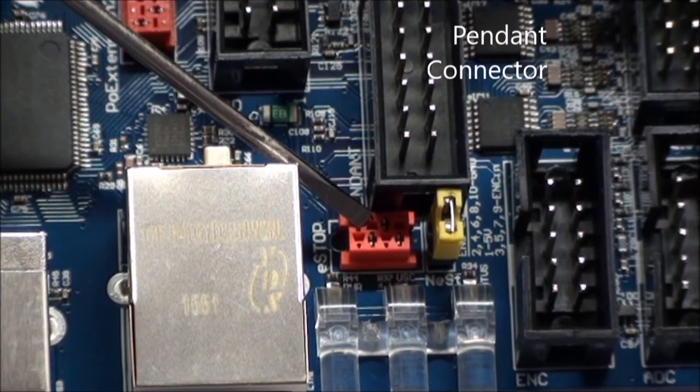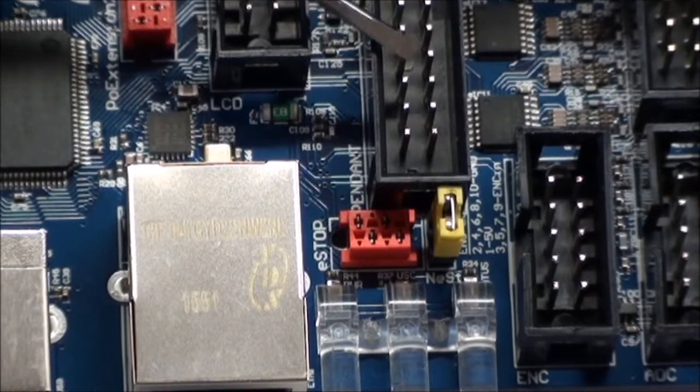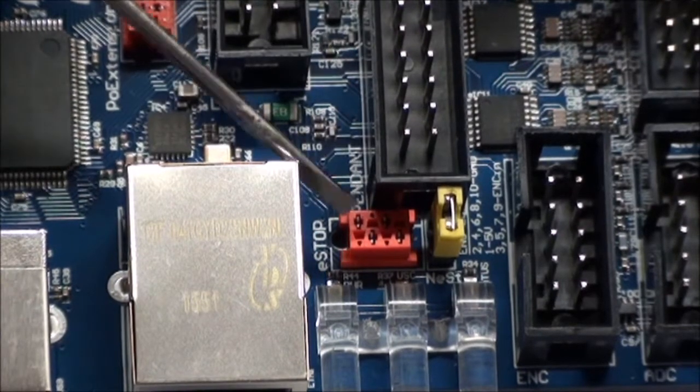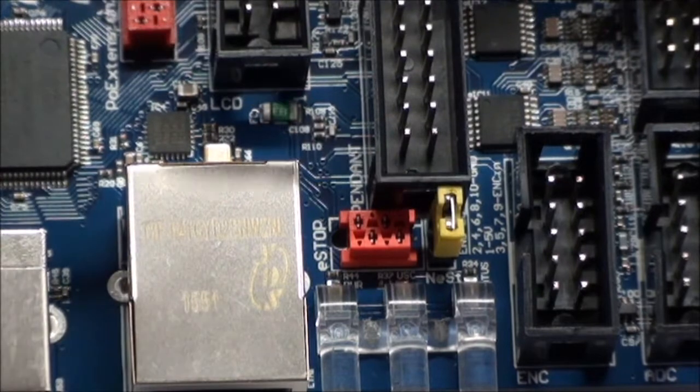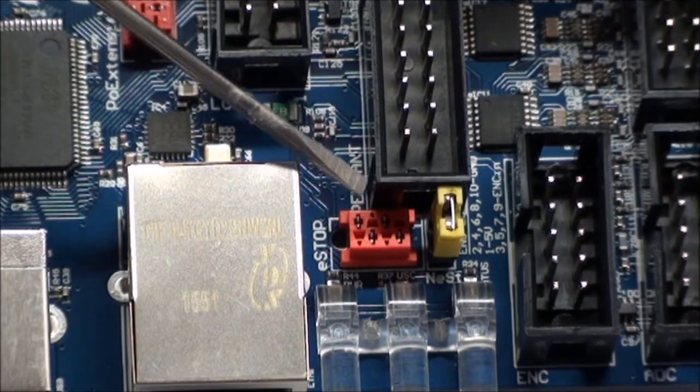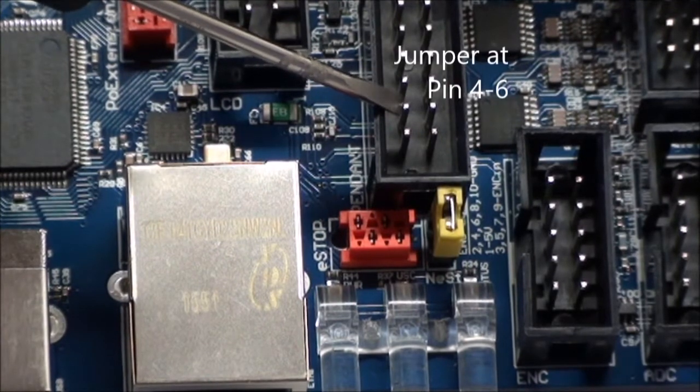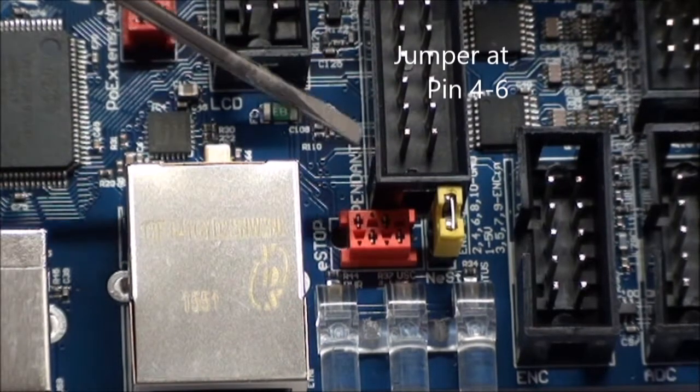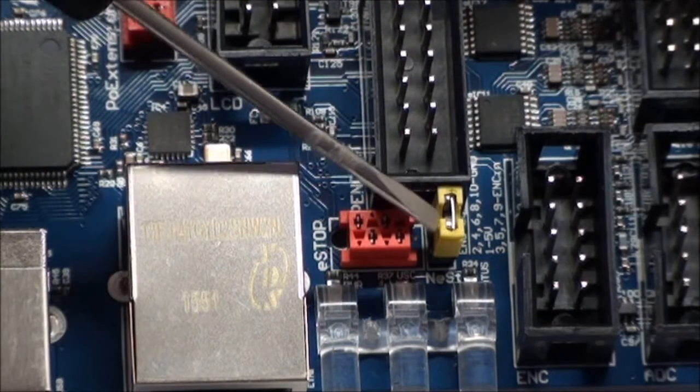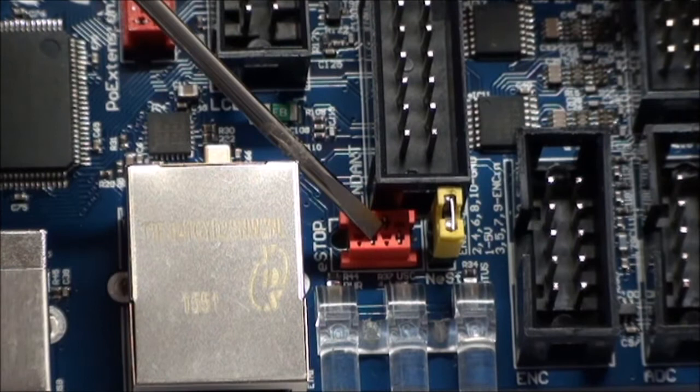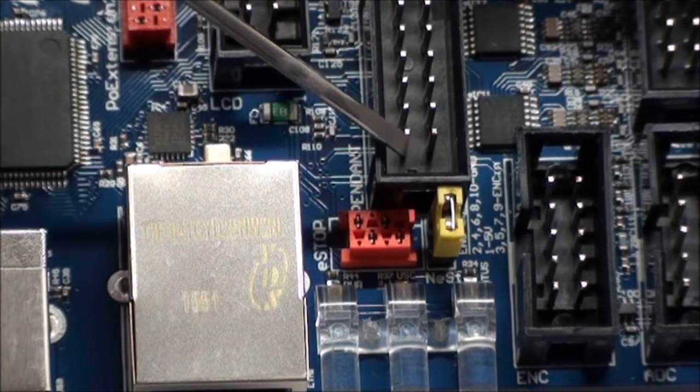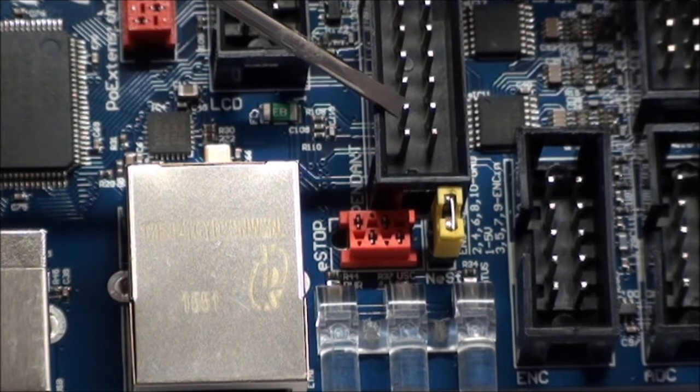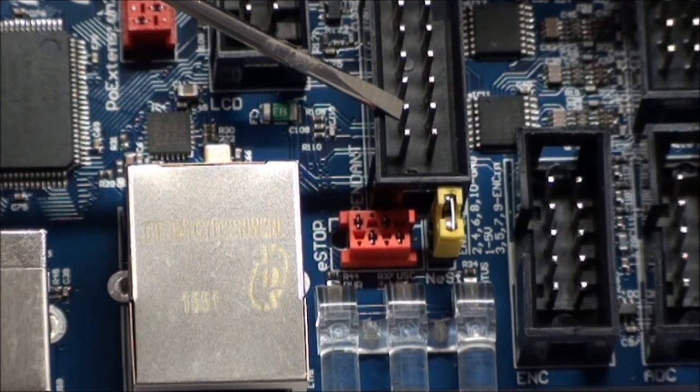You can have either zero e-stop, you can have one here or here, or you can have one here and here, so zero, one, or two. If you have zero, you essentially need to add a second jumper here. If you want to have only the pendant, you will keep this jumper that shortcuts pin two and three on this connector, and then you will add the cable for the pendant, and then this four and six pins will then be connected to the e-stop in the pendant.